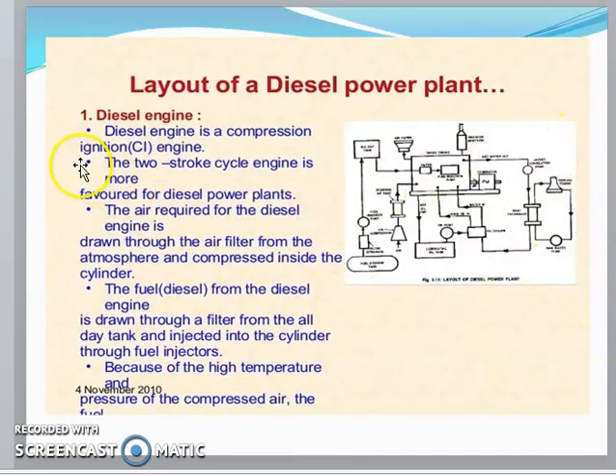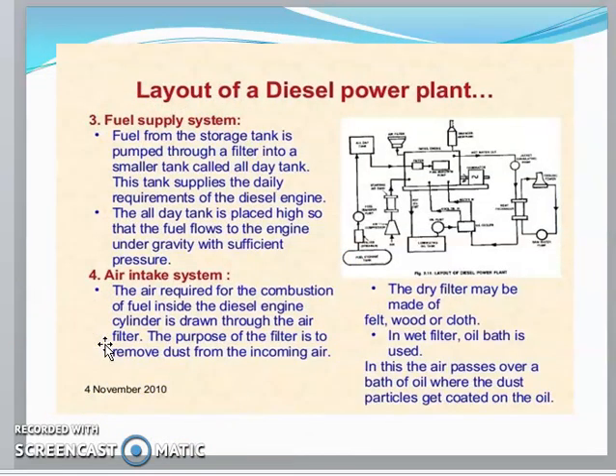This is a simple layout of a diesel engine. The diesel engine is a compression ignition engine. The fuel supply system consists of fuel from the storage tank pumped to a filter into a smaller tank called the day tank, which supplies the daily fuel requirements. The day tank is placed high so that fuel flows to the engine under gravity at sufficient pressure.